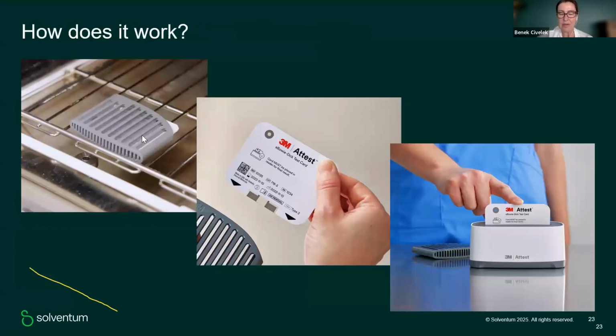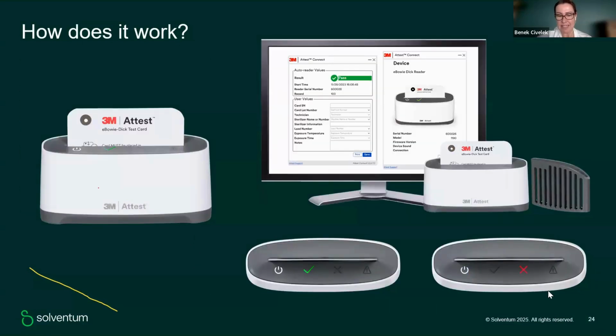We put the test card inside the card holder and place it in exactly the same way that we place a test pack, over the drain. When we take it out, you will see there is a hole and around it a darker color, which is an exposure indicator, meaning the test card has been exposed. But it doesn't tell you anything about pass or fail. What you have to do is put it inside the autoreader, and within 5 seconds you will see either a tick, which means a pass, or a fail, which means there was not sufficient vacuum or steam penetration.